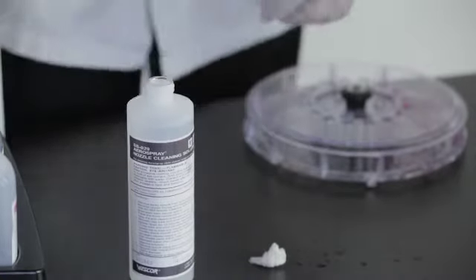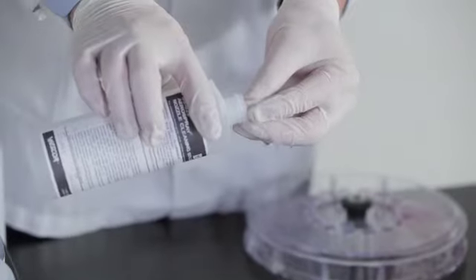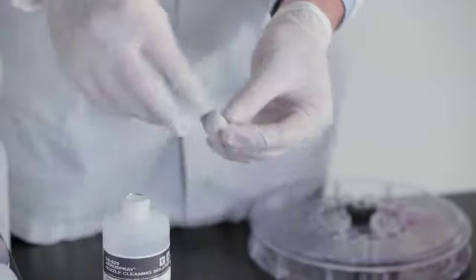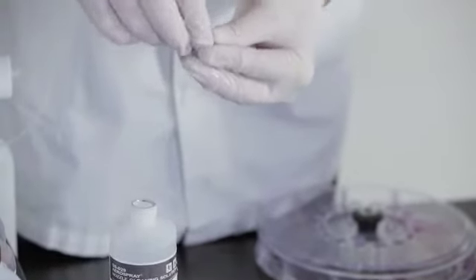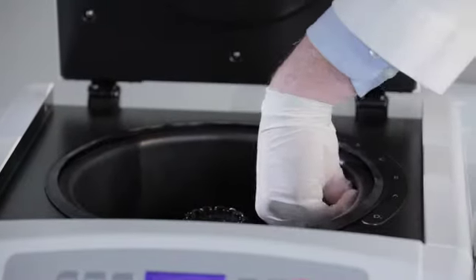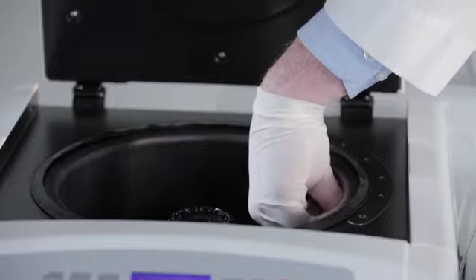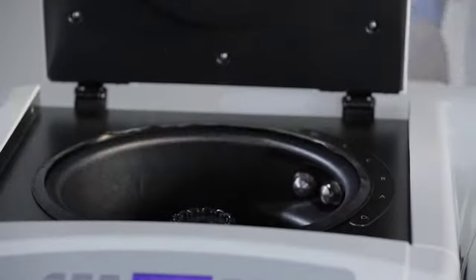Preventive maintenance for the TB stainer includes special attention to the B and C nozzles. These nozzles can become plugged easily. It is recommended to use the nozzle caps for these nozzles. Put a piece of paper towel soaked in nozzle cleaning solution in the cap, and then fit the cap over the B and C nozzles. Store the stainer with these caps overnight or when it is not used for more than 4 hours.